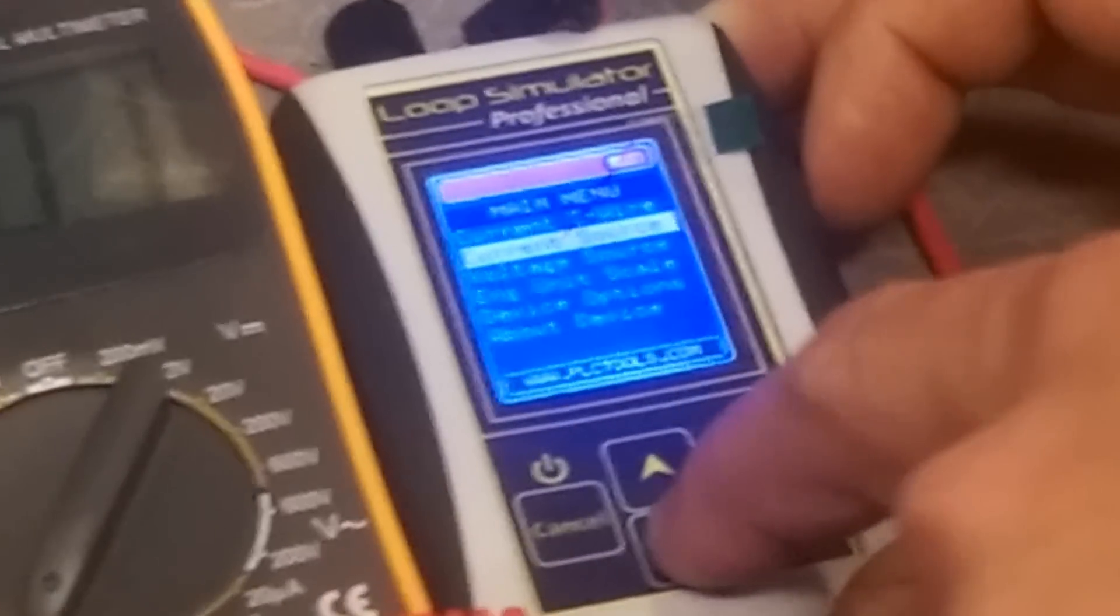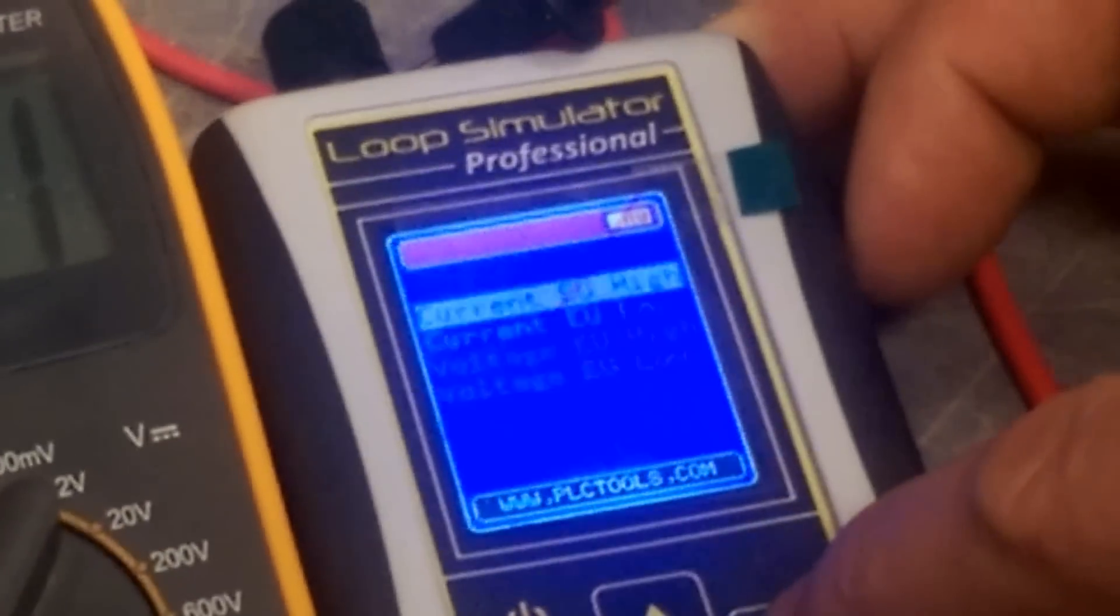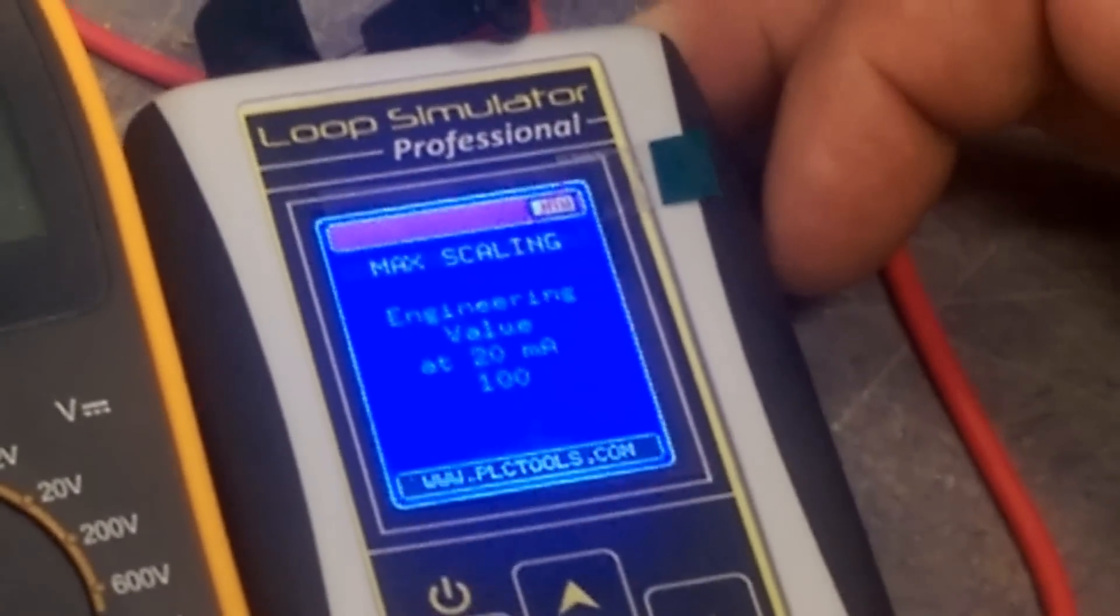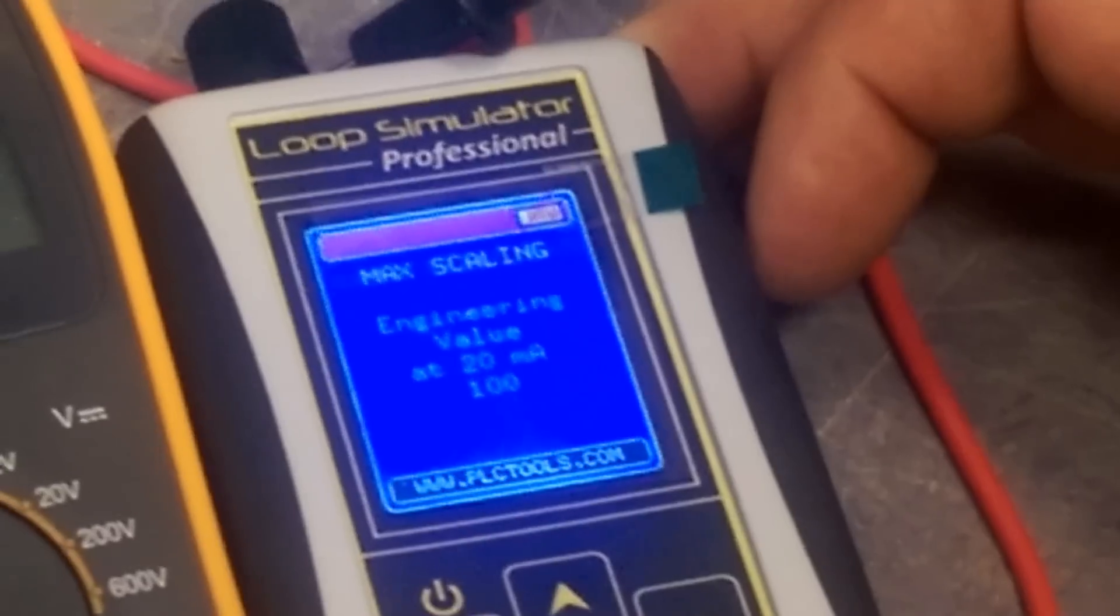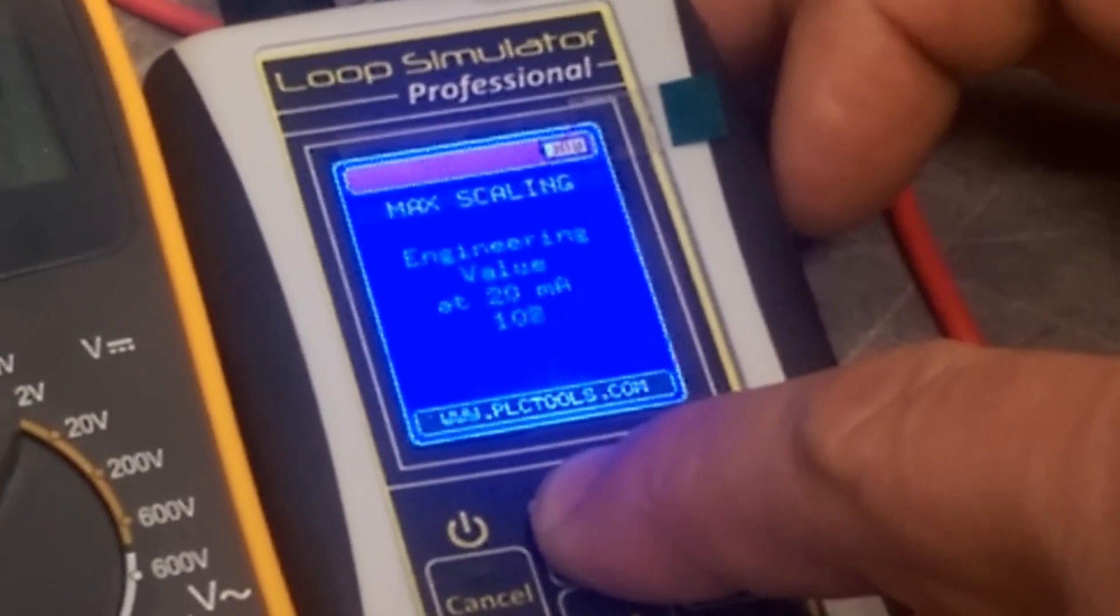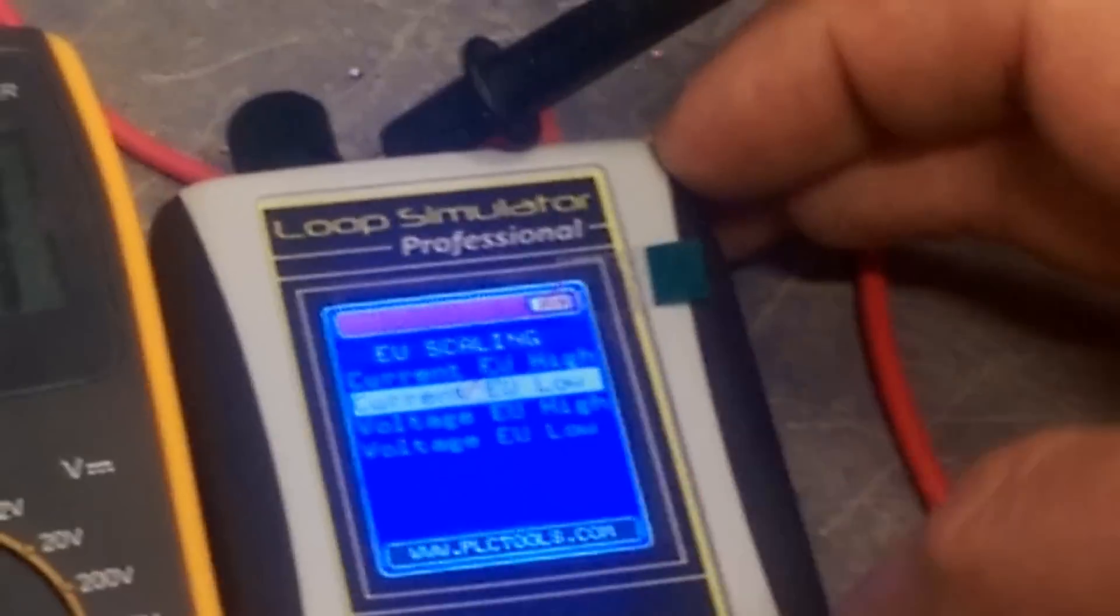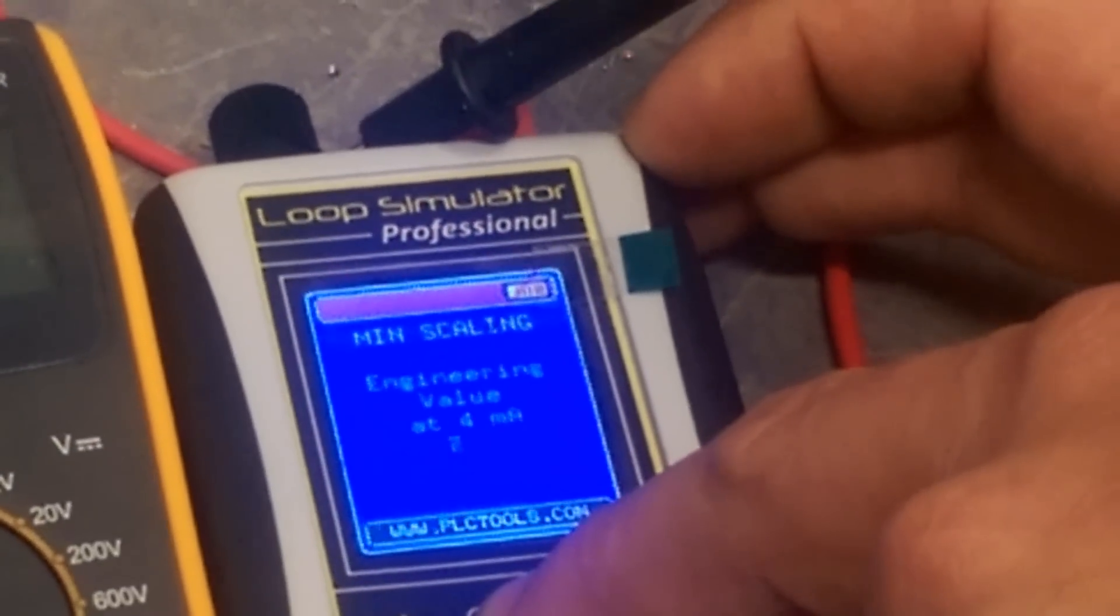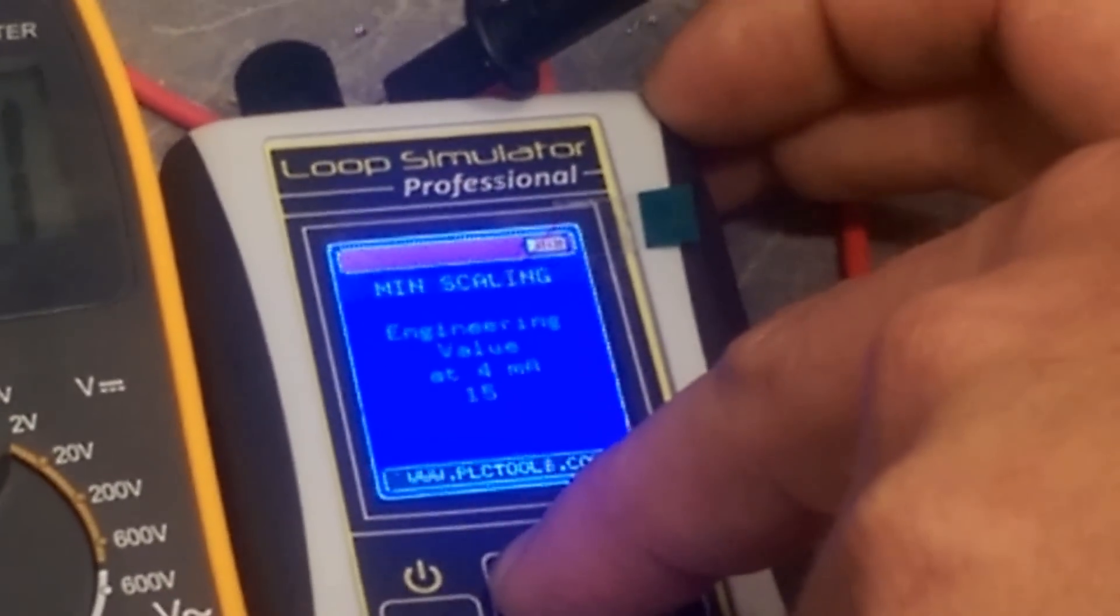Where we have our modes, if you go down, we also have engineering unit scale. And then we have EU high, which since our high value, our 20 milliamp value of our temperature probe is going to be 140, I'm going to put this up at 140. And our EU low, I am going to put it 32, because that is the low range of our temperature sensor.